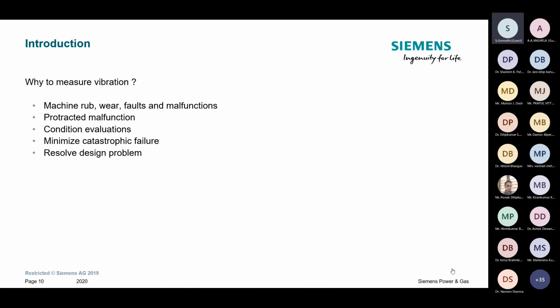If I talk numbers, it's less than 1 millimeter gap during operation. So if it's rotating at 3000 rpm and it touches the stationary part, you'll either have material rub and wear, or a failure happens—the blade will fail or deform. We don't want that, right? And we want to stop malfunctions.